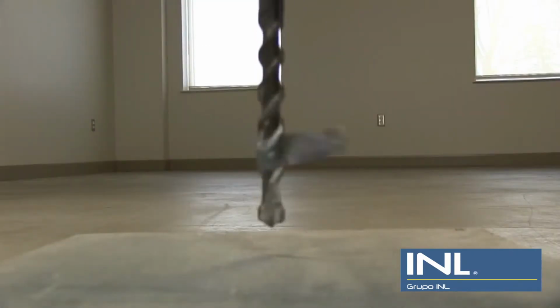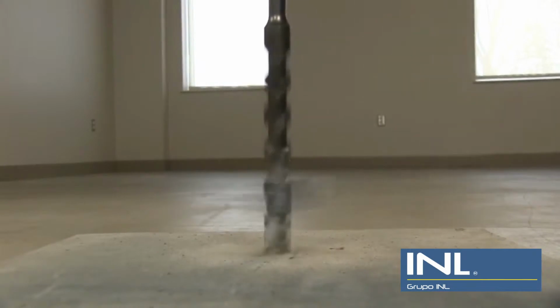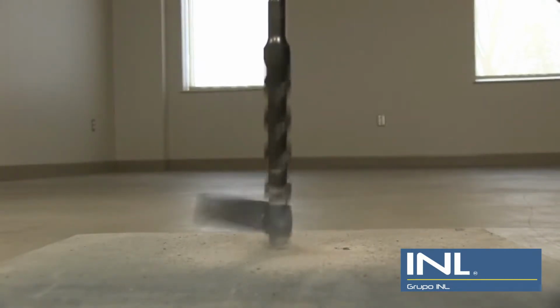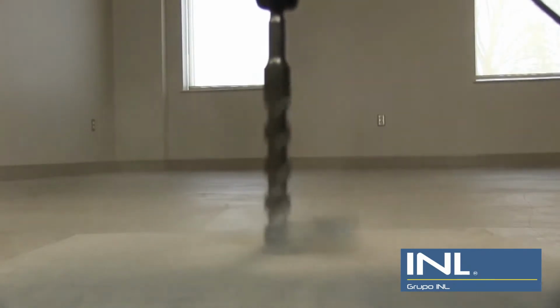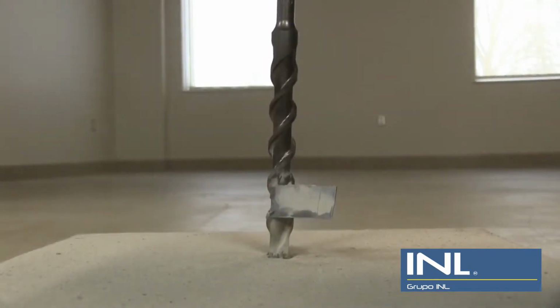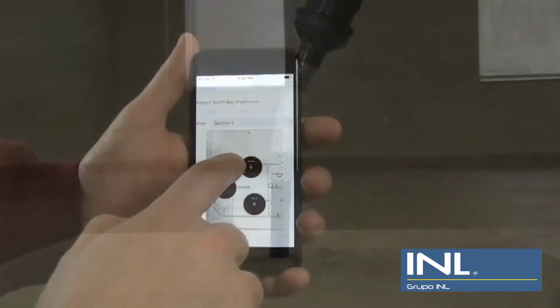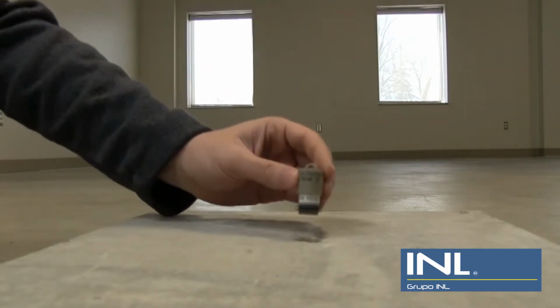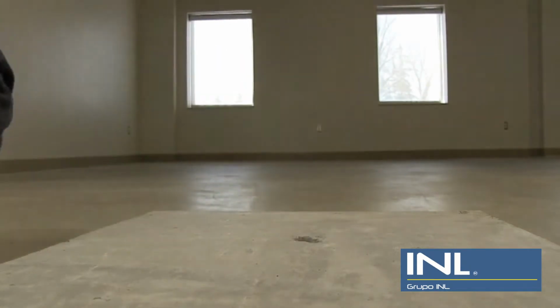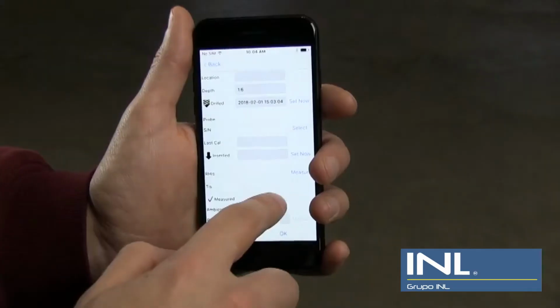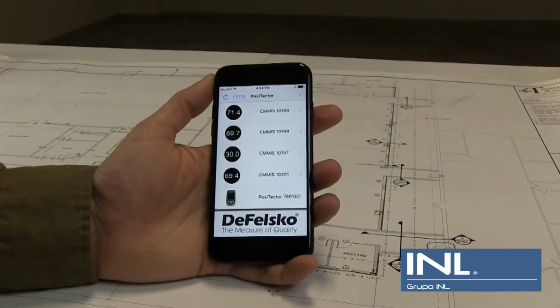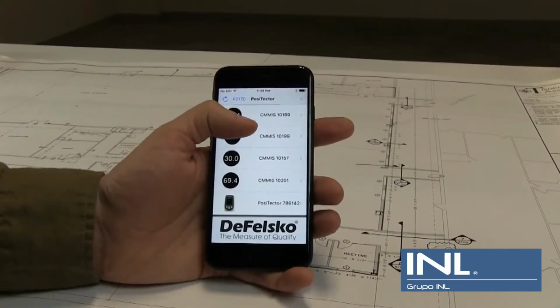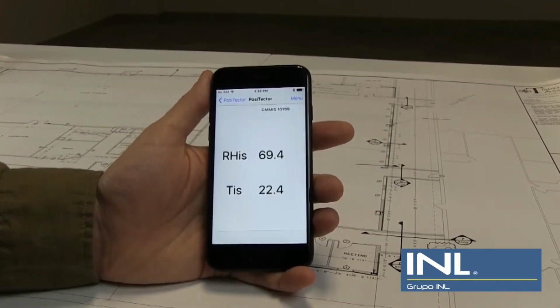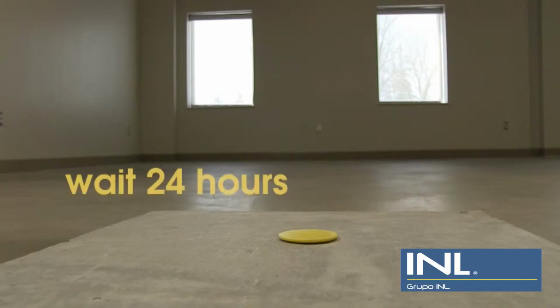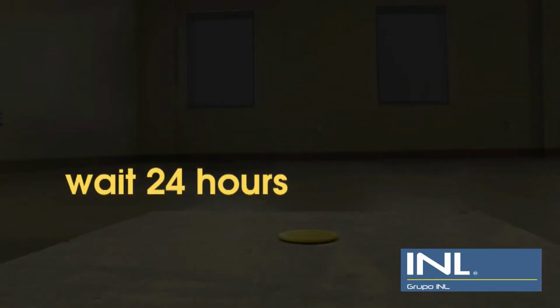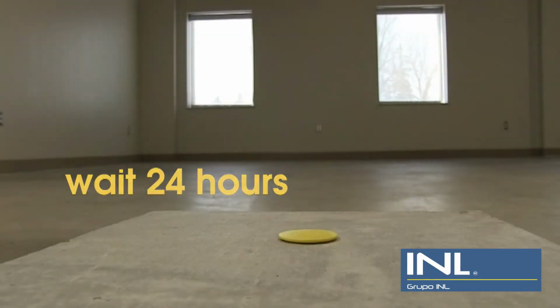Using a hammer drill and 3/4 inch drill bit, drill to the required depth, 40% of the slab thickness if it is drying from one side only, or 20% of the slab thickness if it is drying from two sides. Clean any debris from the hole and note the time the hole was drilled in the app. Finally, insert the probe into the hole and use the yellow cap to seal it. Note the time the probe was inserted using the app. The probe begins measuring immediately and readings can be displayed at any time using the PosiTector app or PosiTector Advanced instrument. However, F2170 requires waiting 24 hours for conditions in the hole to equilibrate before measurements are recorded.